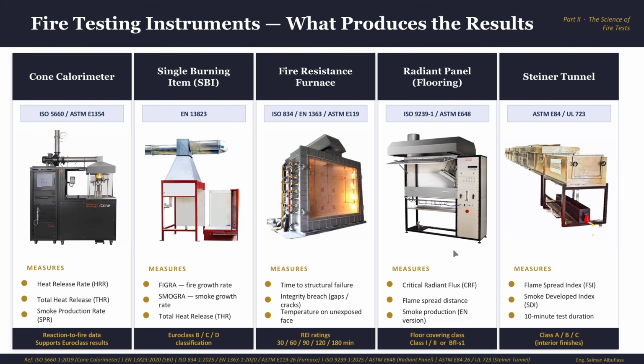And why does this even matter? Well, because in a fire, the floor is probably the last surface to ignite. But when it does, if that is a means of egress route, it cuts it off entirely. So technically, I don't want a highly flammable floor in a hospital corridor or an escape route or a stairwell or a corridor that leads to an exit. I need it to be safe.